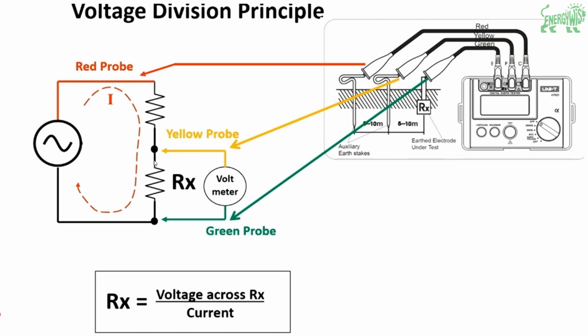So if we measure on the ground electrode, the resistance will be equal to the voltage across Rx divided by the current. Considering the IEEE, if we measure between 0 and 5 ohm, that will be the correct one. There is no need for another ground rod, so we can proceed and approve it. But if it is greater than that, we have to add another ground rod, or we have to check the system. So this is how we can measure the earth resistance using the UT521.